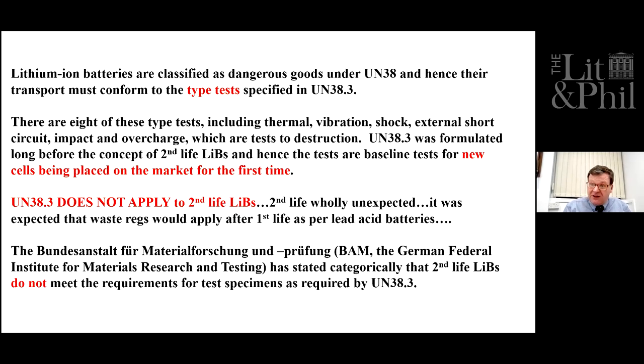People still think of lithium-ion batteries like lead-acid batteries. A lead-acid battery has a first life, and then it's recycled - that's what was assumed when UN 38.3 was written. So UN 38.3 and everything that comes from it does not apply to second life batteries - it only applies to batteries being placed on the market the first time. That means type tests, which we know - and as you can see, BAM agrees - are not valid for second life batteries. And indeed, it doesn't matter, because UN 38.3 doesn't apply.